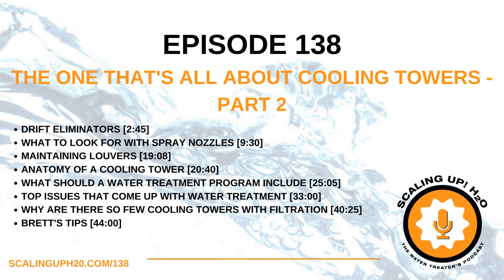Yeah, ideally you have some sort of feeding system so you're not having those granulars just sit on the raw metal. Yikes, especially an oxidizer. Yep, so you've just got to watch the overfeeding of the oxidizing biocide, because the corrosion we've seen is what's happening.